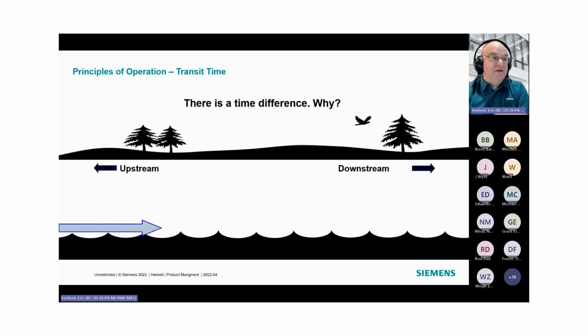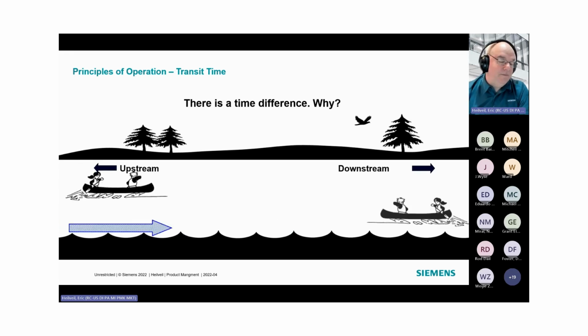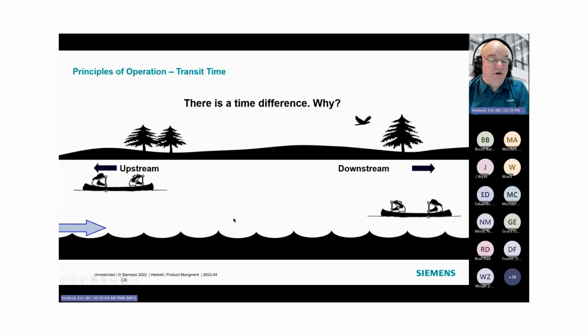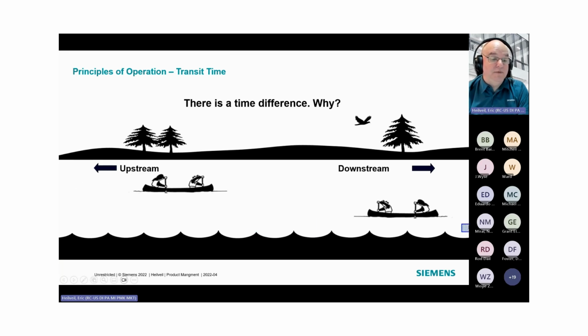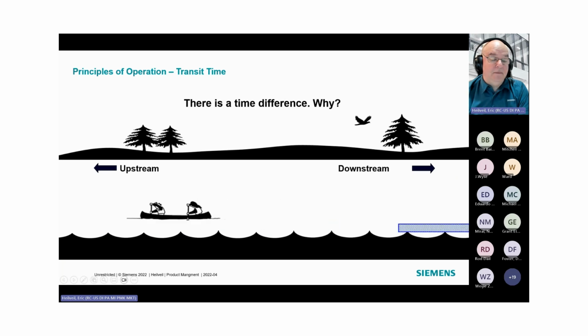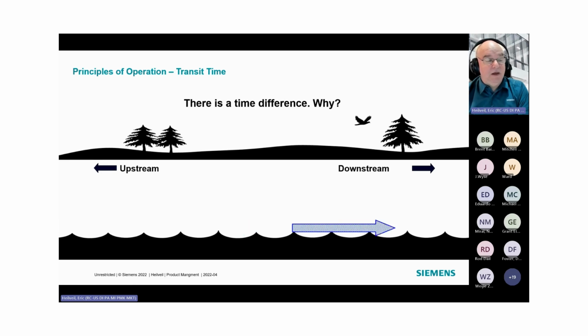Now, if you can imagine this graphic of a stream was a pipeline, and the canoers on the pipeline, the canoers that are going downstream with the current will arrive much faster than the poor guys that have to canoe upstream, just like that. So the time difference between the people going upstream and the people going downstream is directly related to the speed of the flow in the stream or the river. So that transit time between those 2 points can tell us how fast the current is.